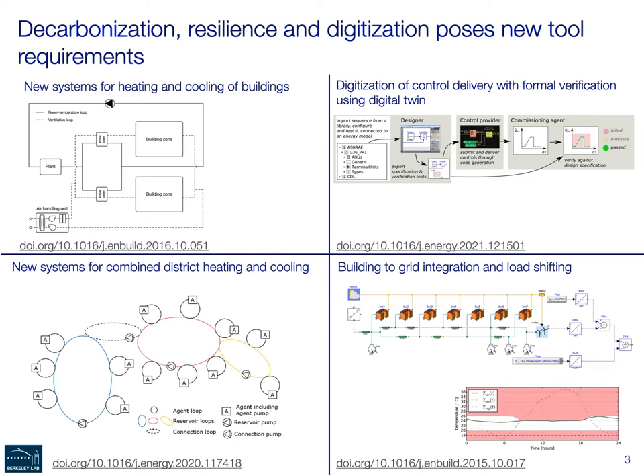We see somewhat related trends in district heating and cooling systems, where we now have new fifth-generation combined district heating and cooling systems with one tempered loop that provides a reservoir from which buildings can exchange heat and cooling. At every building, temperature is boosted up or down to exactly what that building needs, giving very high efficiency. We can modularly build out systems and share waste heat, waste source potential, and storage potential between different buildings or districts of a city.